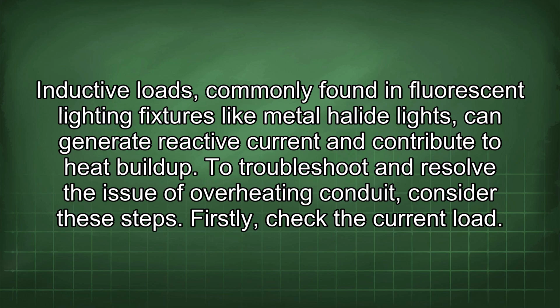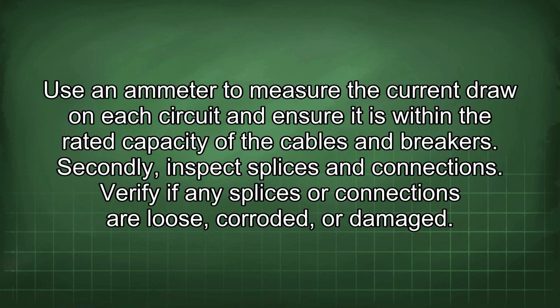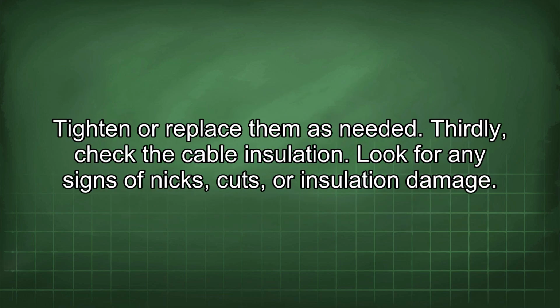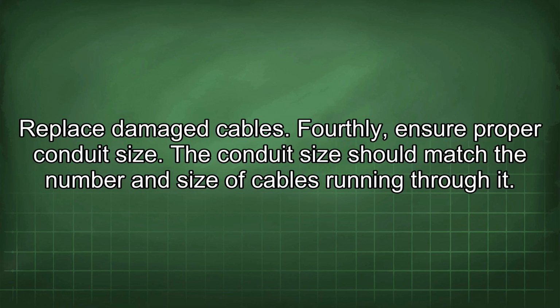Firstly, check the current load. Use an ammeter to measure the current draw on each circuit and ensure it is within the rated capacity of the cables and breakers. Secondly, inspect splices and connections. Verify if any splices or connections are loose, corroded, or damaged. Tighten or replace them as needed. Thirdly, check the cable insulation. Look for any signs of nicks, cuts, or insulation damage. Replace damaged cables. Fourthly, ensure proper conduit size.